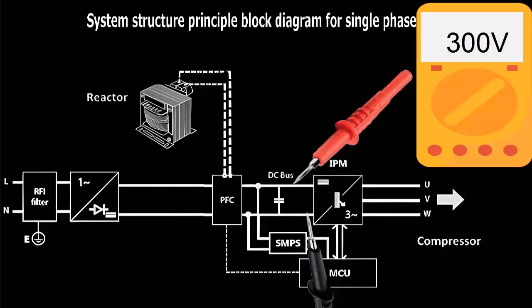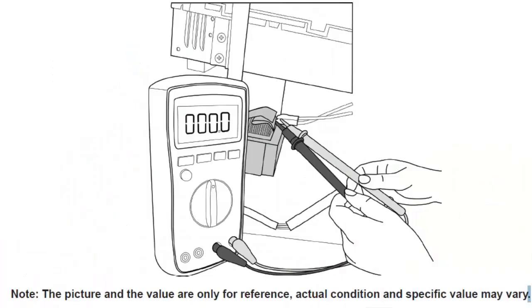11. Before performing any replacements, it is recommended to measure the electrical continuity in the reactor located in the outdoor unit, using a multimeter in the continuity or resistance range. To do this, disconnect the reactor. The normal value should be close to 0 ohms. Otherwise, the reactor is likely faulty.